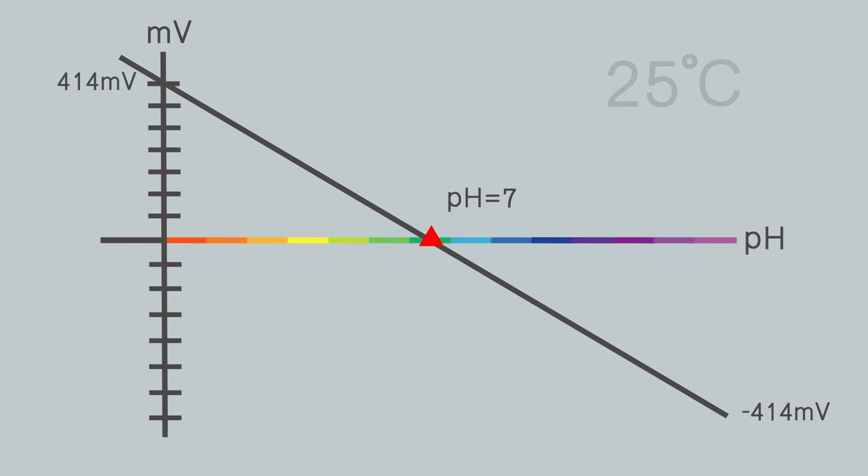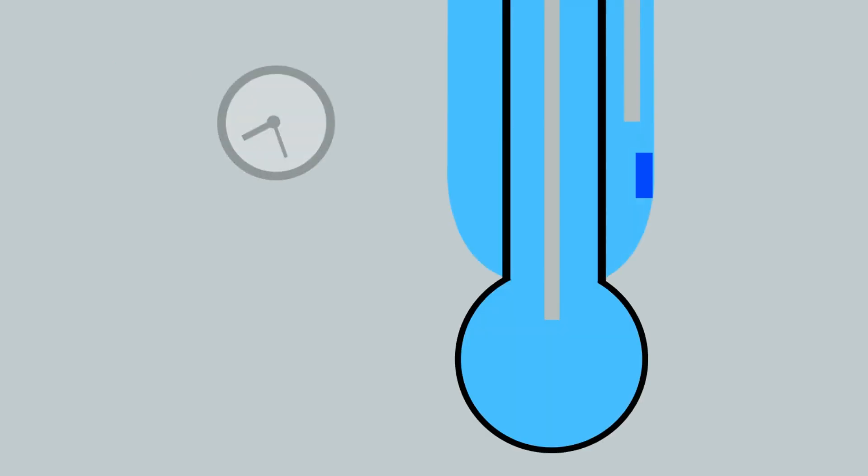As noted above, the theoretical potential at pH 7 is 0 millivolts, but actually, the potential is usually between negative 47 and 47 millivolts because of zero drift and asymmetric potential.